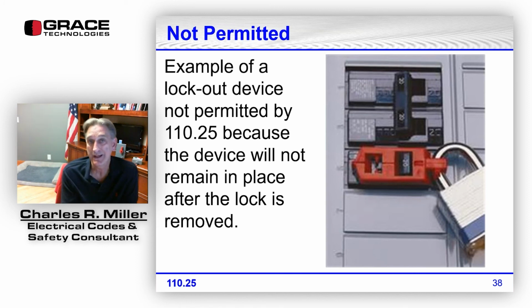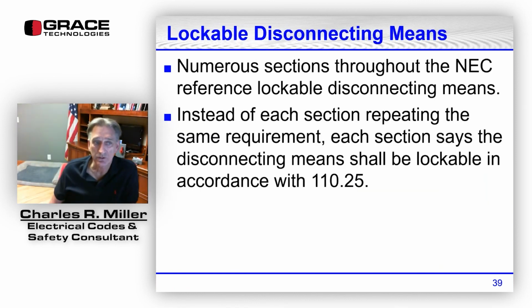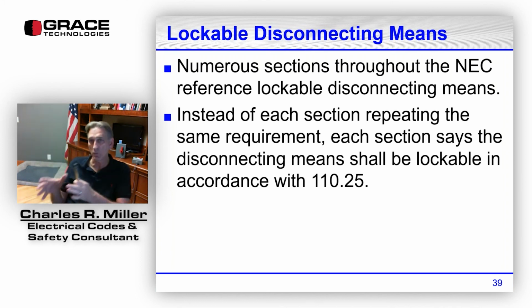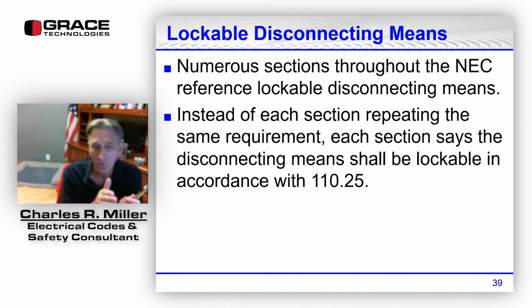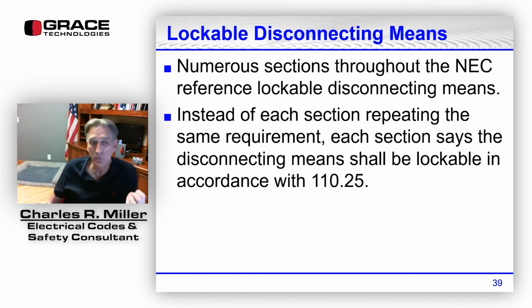plant, and it's normally not required to have a lockout device on it. We can absolutely use these aftermarket devices to do our lockout tagout. Numerous sections throughout the National Electrical Code reference lockable disconnecting means. Instead of each section repeating the same requirement, and that's what I mentioned a few minutes ago, each section says the disconnecting means should be lockable in accordance with 110.25. So it was great that they took all the different wordings out of all these different sections throughout the NEC, and they just reference now that it has to meet the requirement in 110.25.